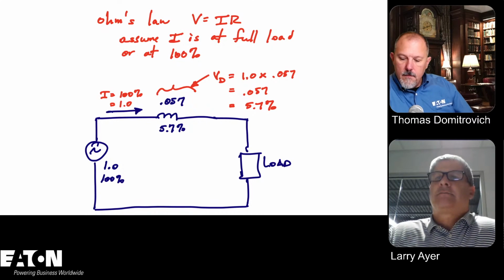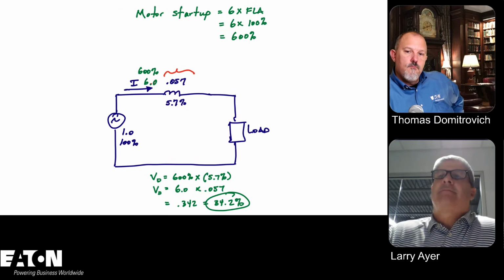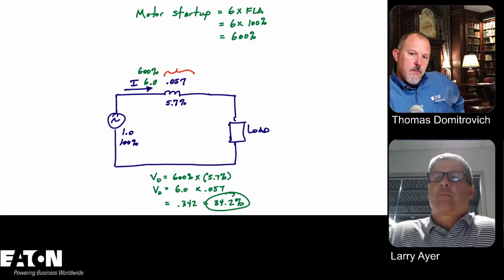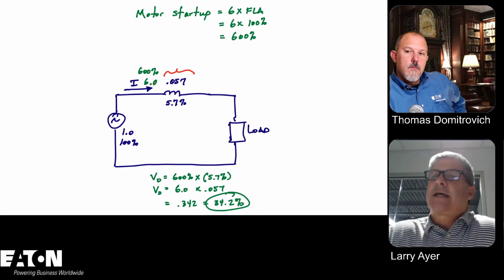If you can go to the next slide, if I say I got motor startup current, my motor startup current is 6 times full load or 6 times 100%. So if I convert everything to percentages here, if my voltage is 1 and my current is 6 times full load, if I'm trying to calculate my voltage drop, 6 times 5.7% or 6 times 0.057 gives me a voltage drop of 34.2%. So this is well above the 15% startup. So if you have a transformer that's situated somewhere in the feeder between the service and the fire pump controller, you know that you have to significantly oversize that transformer, probably at least 2 times or more to really make this thing work.